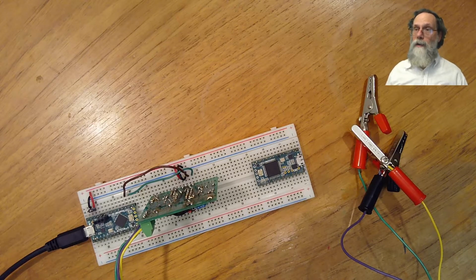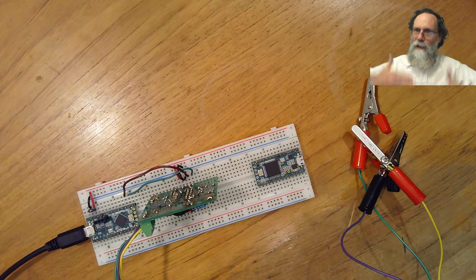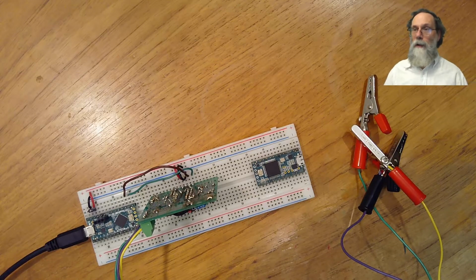There are four wires used for what are called the limb leads, because they're connected to the arms and the legs. And then there's six more chest leads, because they're connected to the chest. So that makes a total of 10 wires. But those 10 wires are interpreted in 12 different differential channels. There are six channels that are associated with the vertical plane, and those are just derived from the four limb wires. And there are six horizontal plane, they're derived from the six chest electrodes.